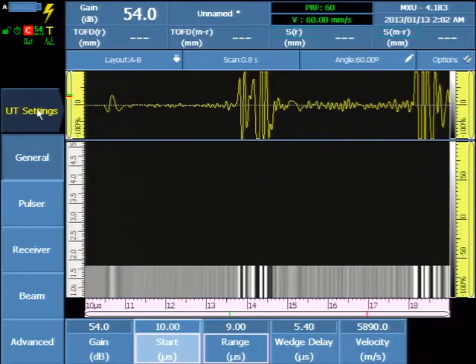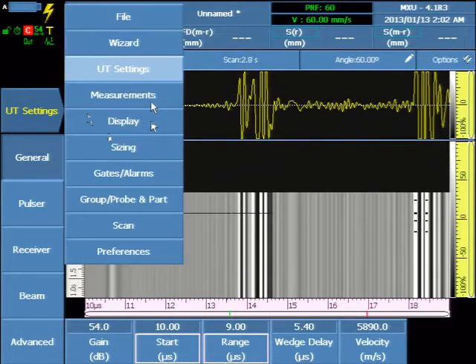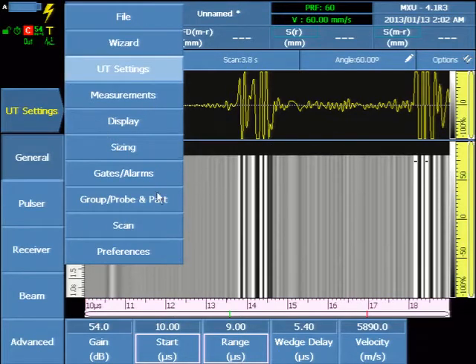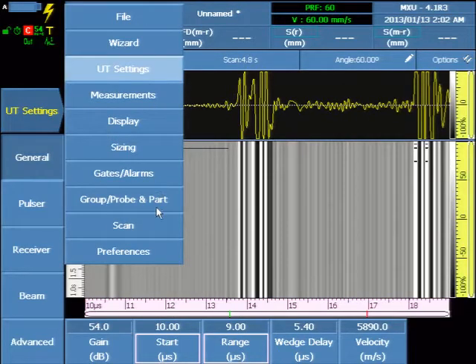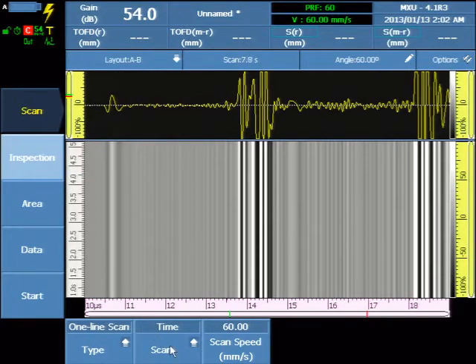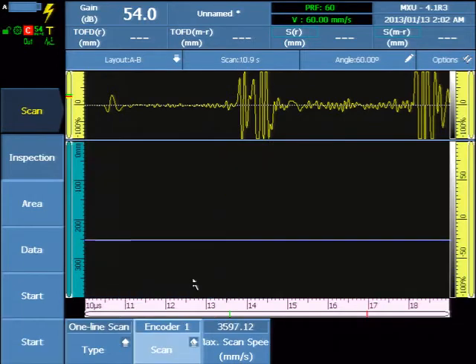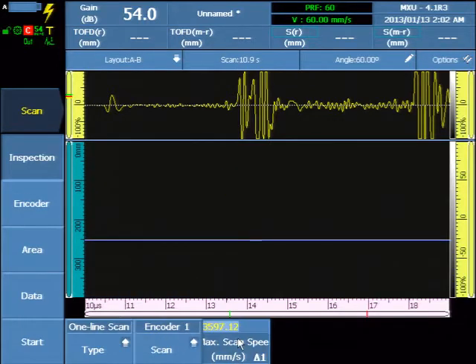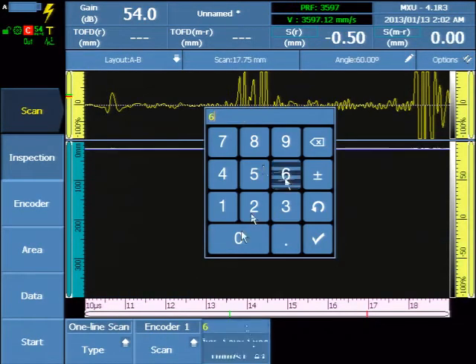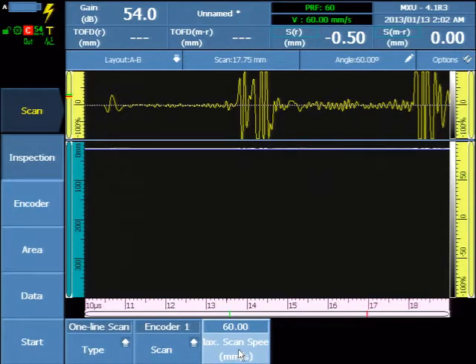Continue the configuration to the Scan menu, and change the default from Time to Encoder 1. And enter a scanner speed of 60 millimeters per second, or appropriate with your mechanics, whether it's a manual push scanner or automated.